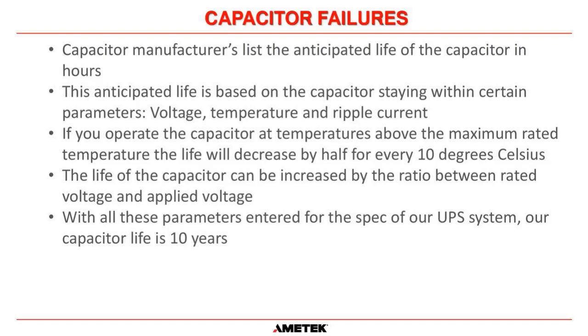Okay. And with all of these parameters taken into consideration and then entered for the spec of our UPS system, the design life of the main DC capacitors that we install within our UPS turns out to be 10 years if you operate it within the parameters on the data sheet of our UPS.